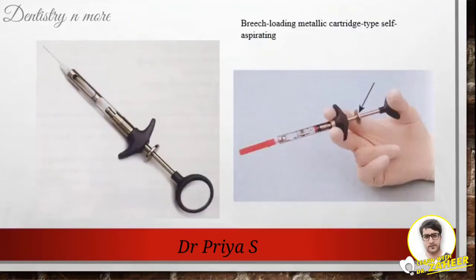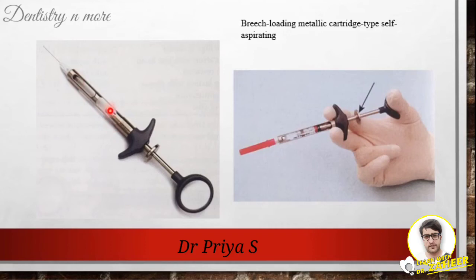With commonly used breech-loading metallic cartridge type syringes, an aspiration test must be carried out purposefully by the administrator before or during drug deposition. However, studies have shown that many dentists don't purposefully perform an aspiration test before injection. Therefore, to increase the ease of aspiration, self-aspirating syringes were developed. These syringes use the elasticity of the rubber diaphragm in the anesthetic cartridge to obtain the necessary negative pressure for aspiration.